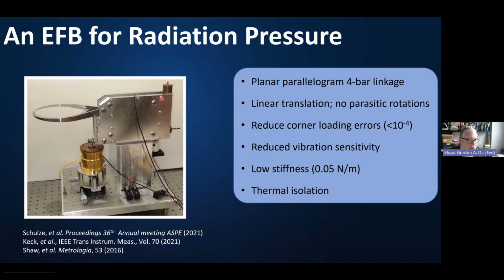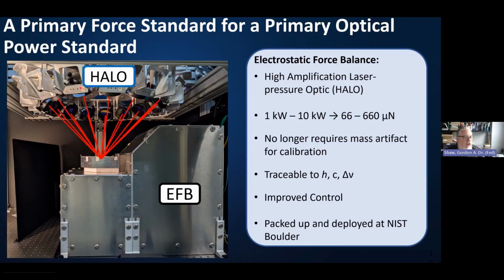And so here is an electrostatic force balance that we built here at NIST and deployed at NIST Boulder that has a high reflectivity mirror fixture here where the laser can reflect. And then we have a capacitor at the bottom to generate a traceable reference force. And so the idea is that we can directly compare the electrostatic reference force to the photon pressure force generated by the laser to calibrate the laser power. And we use this instrument in conjunction. Here is the electrostatic force balance here. It's in an enclosure. We have an instrument called the HALO, which is the high amplification laser pressure optic.